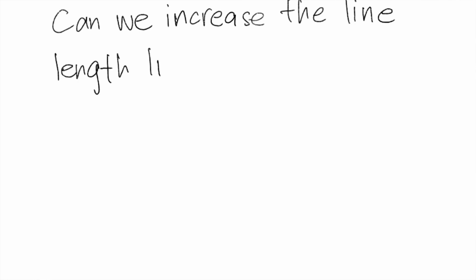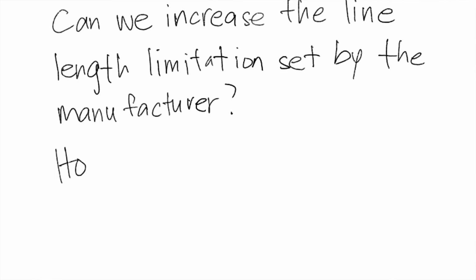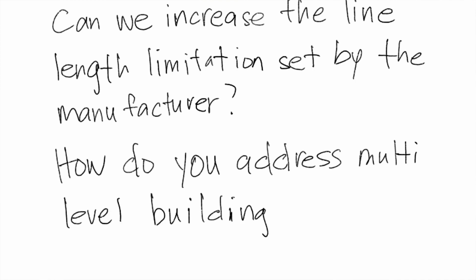The next question I got was, can we increase the line length limitations set by the manufacturer? How do you address multi-level buildings where the vertical line length limitation is less than the total height of the building that you're trying to serve? The short answer is no, we can't increase the line length limitations. Those limitations are there to help the equipment run properly and to ensure that the equipment runs for a long period of time to basically meet the 15 to 20 year life expectancy of a VRF system.